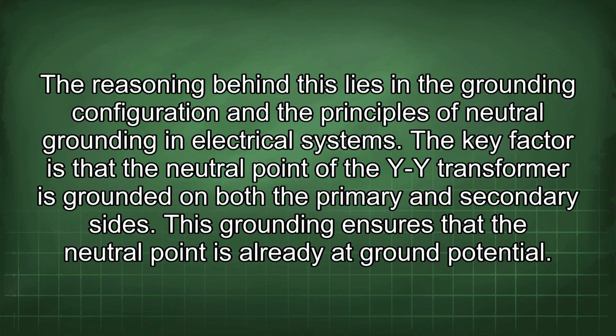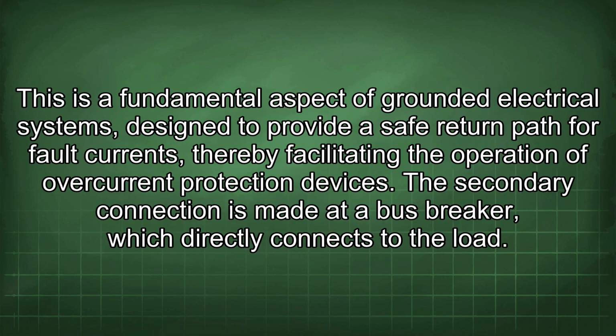The reasoning behind this lies in the grounding configuration and the principles of neutral grounding in electrical systems. The key factor is that the neutral point of the YY transformer is grounded on both the primary and secondary sides. This grounding ensures that the neutral point is already at ground potential. This is a fundamental aspect of grounded electrical systems, designed to provide a safe return path for fault currents, thereby facilitating the operation of overcurrent protection devices.